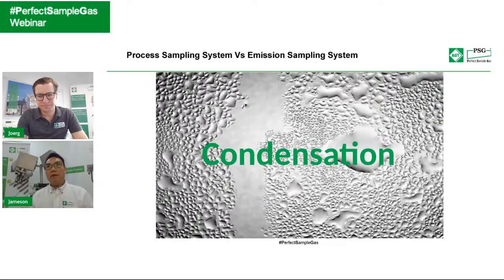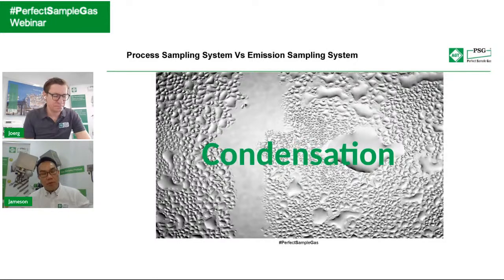So as far as a CEM system is concerned, you realize that there is always a sample pump at the downstream. Why? Because in emissions, 99% of the time, there is negative pressure. This is why you need a sample pump to siphon, to pull the sample out. Different from process, which is normally positive, emission is negative pressure. And when the pump siphons the sample and delivers it to the gas analyzer, after the pump they push, and that pushing becomes positive.